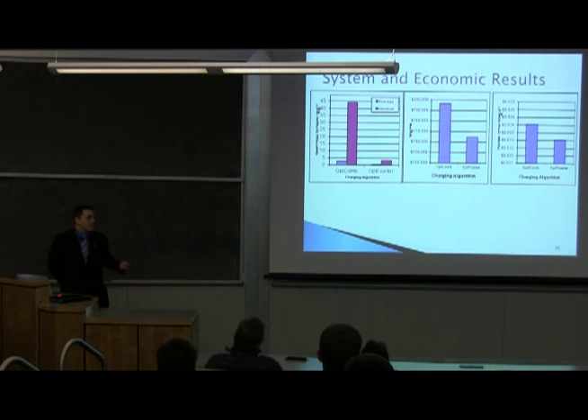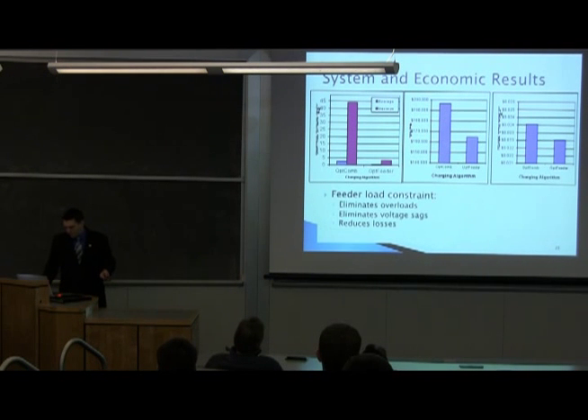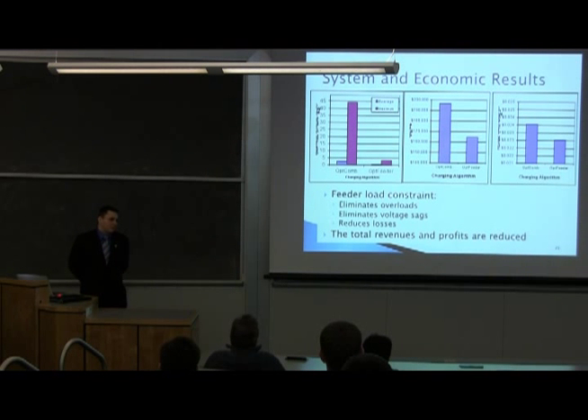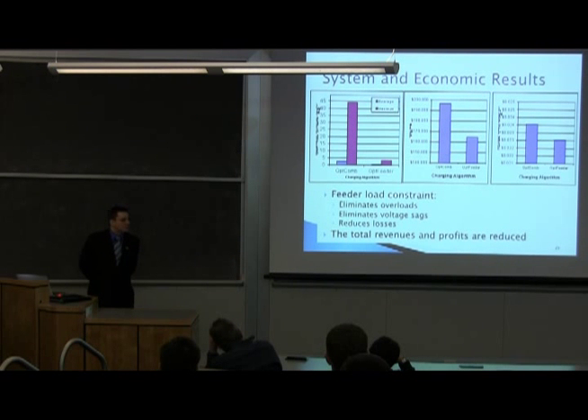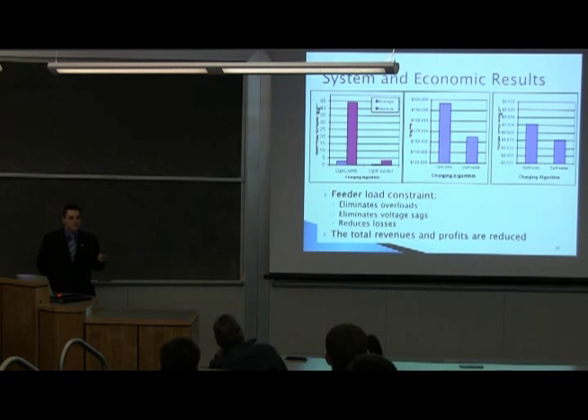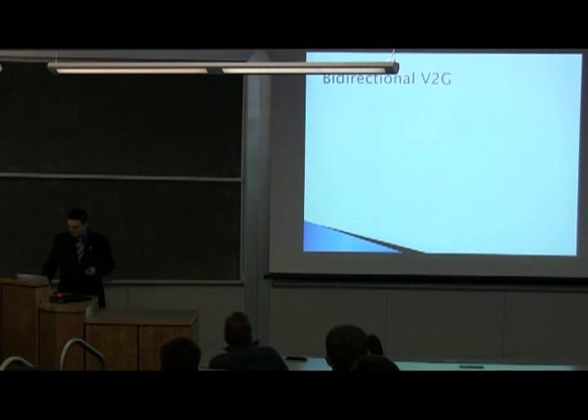So if the aggregator is a third party, you'd say, who cares? Our feeder load constraint can eliminate the overloads, reduce the voltage sags, and reduce the losses—who cares about the aggregator profits? But if the utility is the one doing this aggregation, they can ask whether this is the most cost-efficient way to stop the lines from overloading, or whether, with that much money over 10 years, they'd be better off investing in fixed capacitor banks or bigger transformers. So the economic comparison can be made.